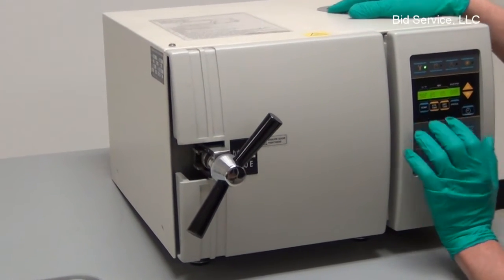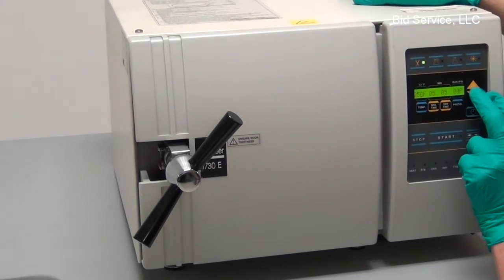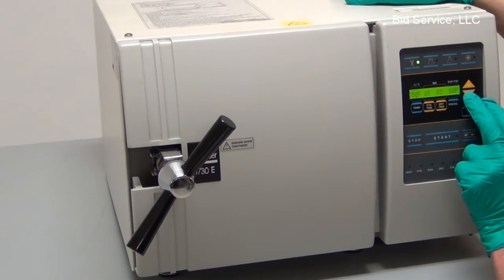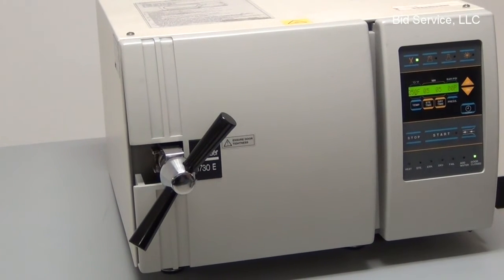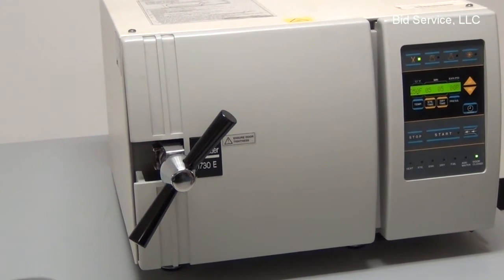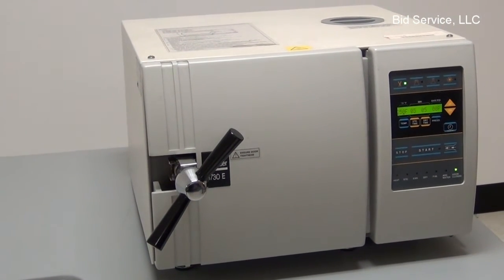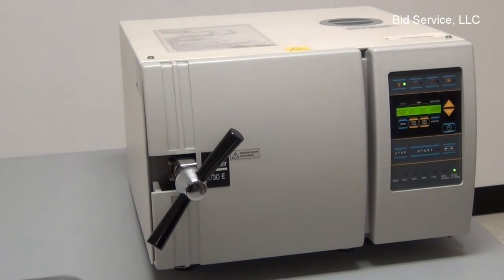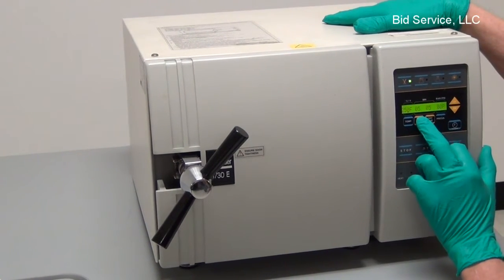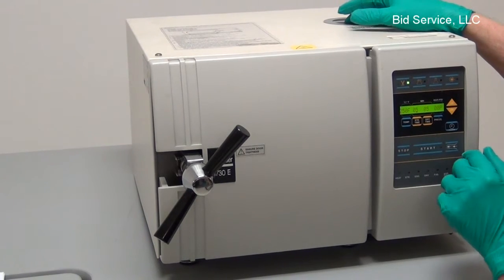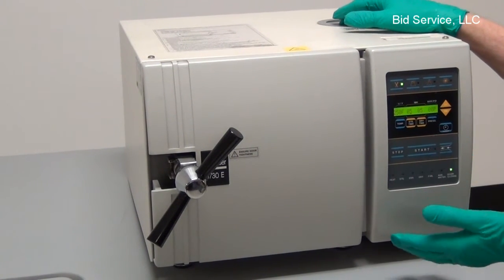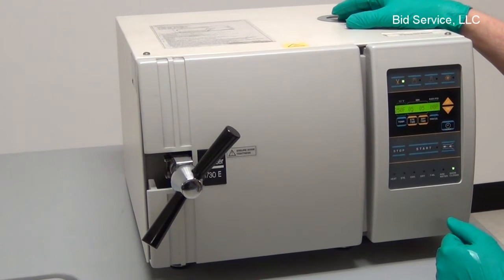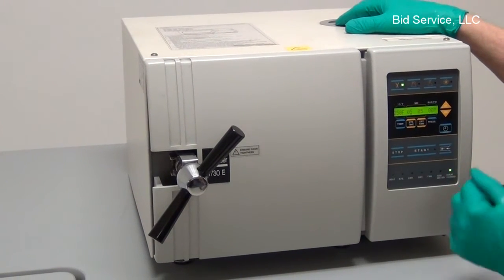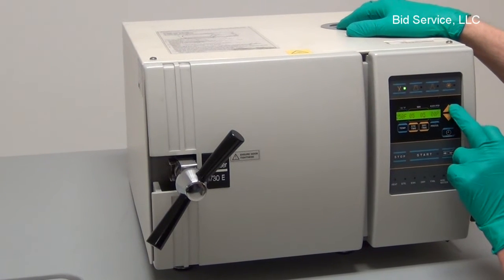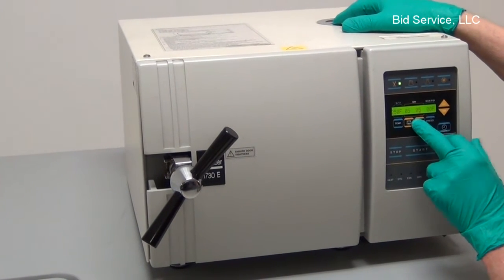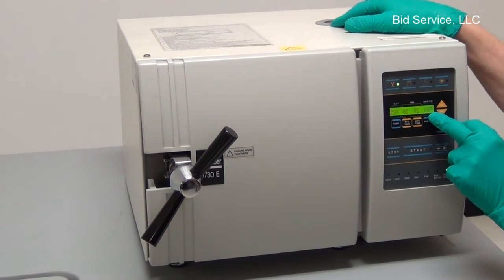You can separately set the temperature by either raising or lowering. It is suggested that for proper sterilization the temperature be set between 250 and a maximum of 276 degrees. You can set the sterilization time from as few as 1 minute up to, I don't remember quite what it is, but it's significant, like several hours if you need to. You can also set the drying time as well. And this last display here is for pressure.